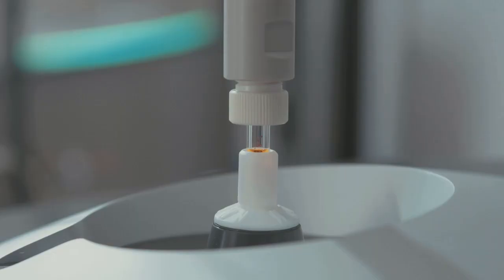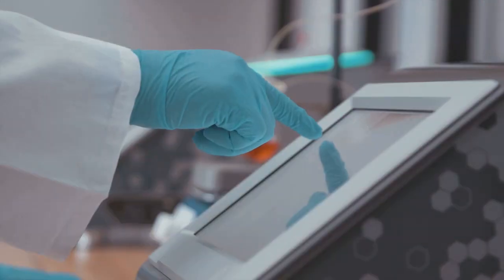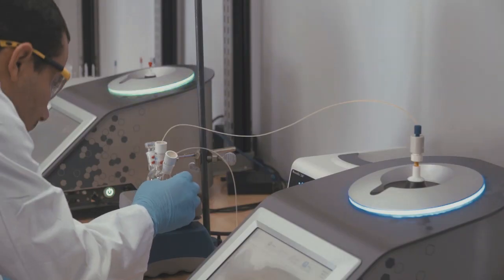Compact NMR is basically like ordinary NMR, but we found that there's a need for many routine experiments to be done right at the point of need. The most important innovation for that was the development of a magnet that could be situated on the bench top and that could be strong enough to be useful for NMR experiments.